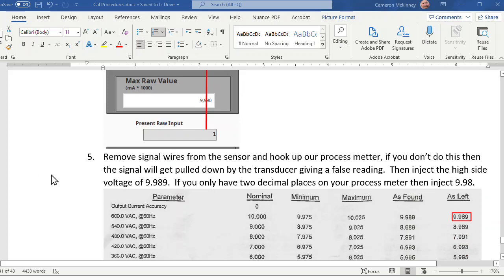Most importantly, you're going to have to remove the signal wires from the sensor, because especially with voltage, if you have anything else hooked up, you're going to load it. In my example, you can leave the ground hooked up, but you've got to get the positive off. It cannot be hooked up when you hook up your process meter, because if it is, you're going to draw the whole circuit down and you won't have a correct calibration.